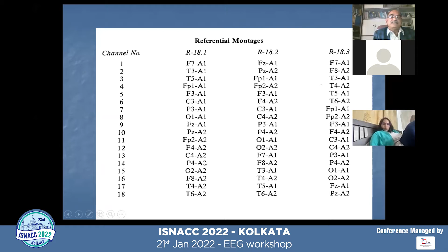Now we have to do the activation procedure if we have to pick up the abnormality in the EEG. What activation procedures can we go for? We can go for eye opening and closure. We can go for hyperventilation, asking the patient to hyperventilate for 3 minutes. Then intermittent photic stimulation: just above the eye, there is a machine called a stroboscope. Through that stroboscope, we can give photic stimulation, that is flickering light. It may be at 1 per second or 5 per second or 10. Gradually, you increase the frequency so that the abnormality can be picked up. And this stimulation can be done in eye open position and eye closed position.